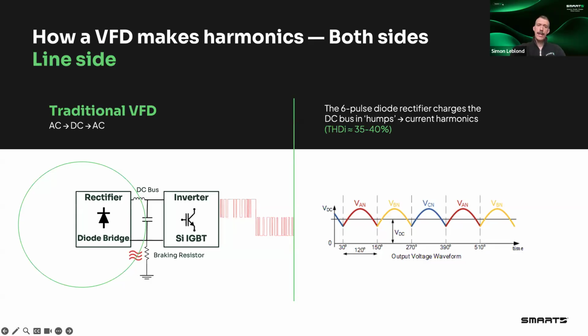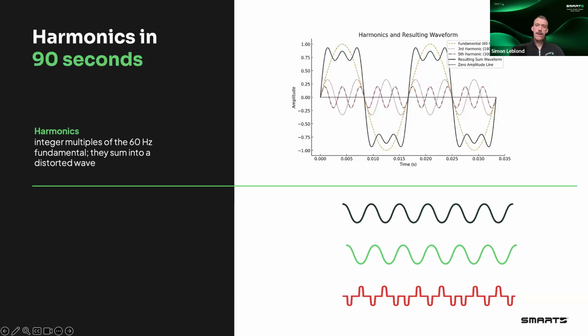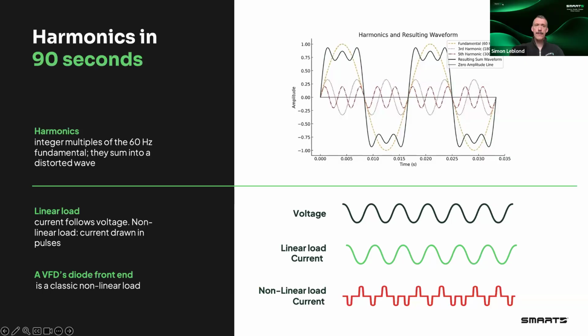For a typical VFD, which has a DC choke, you're going to have around 35 or 40% harmonic content. You could have a VFD without a DC choke, that would be over 70%, but I doubt any of you have installed those in a very long time. So really, that's what's causing the harmonics on the grid. And what those harmonics are, I mentioned it quickly: they're the distorted wave, the integer multiples of the 60 hertz fundamental. And when you sum them up, they come into this black distorted wave. And that's how you see harmonics on the grid.